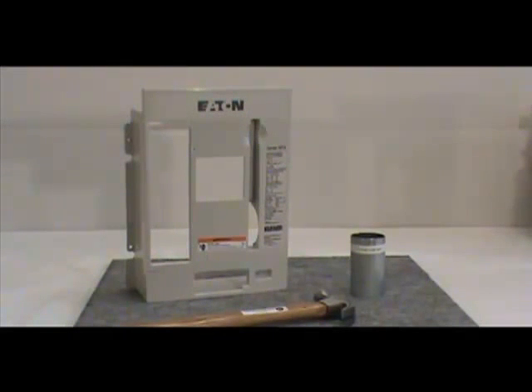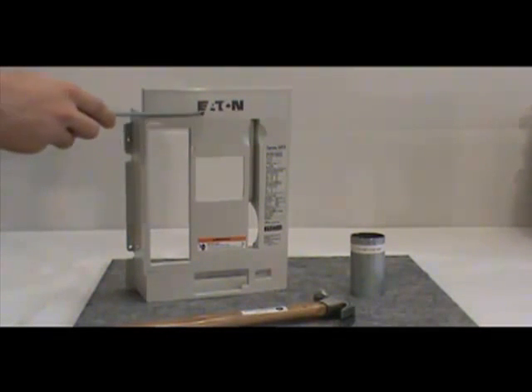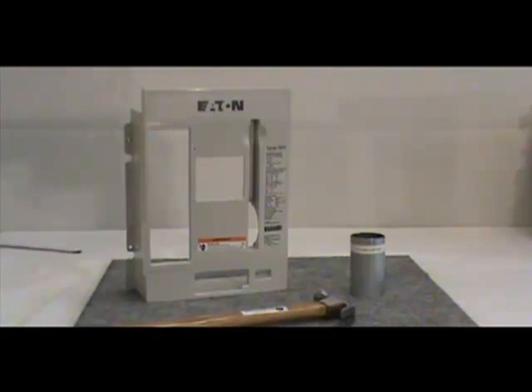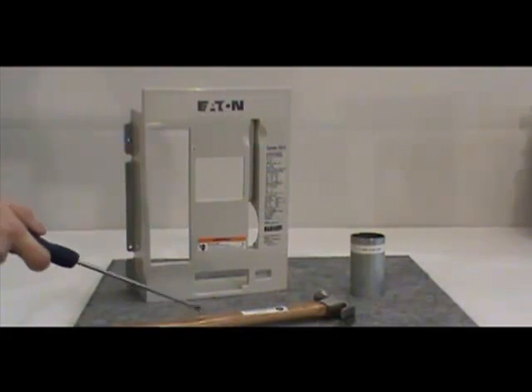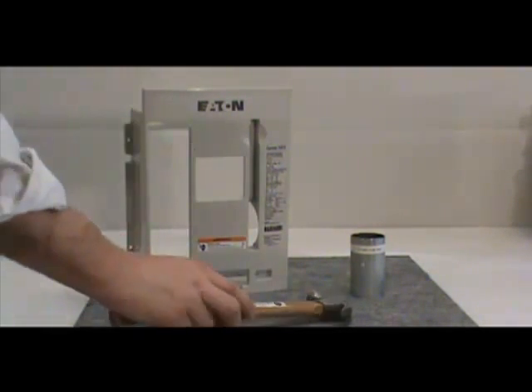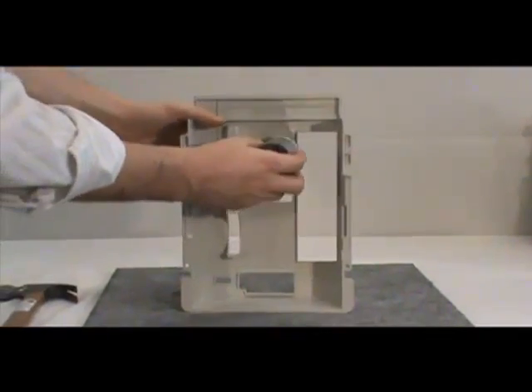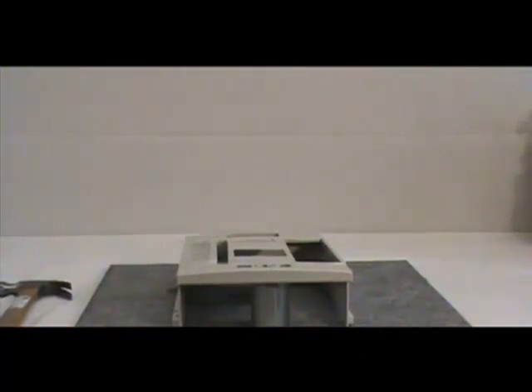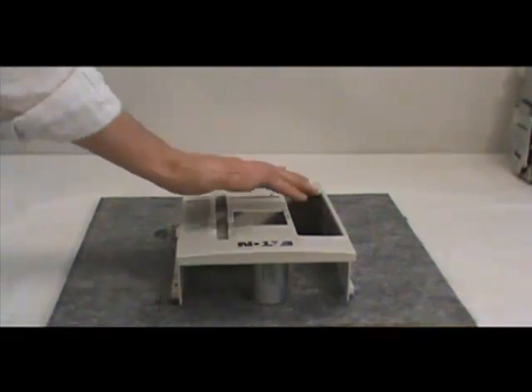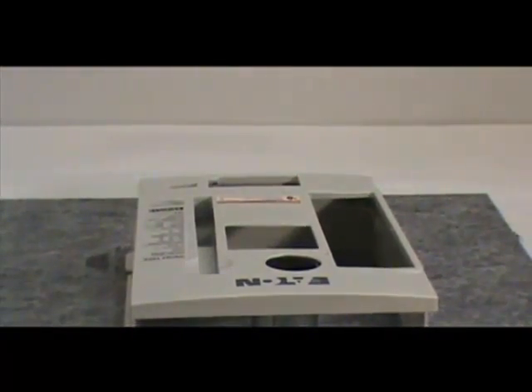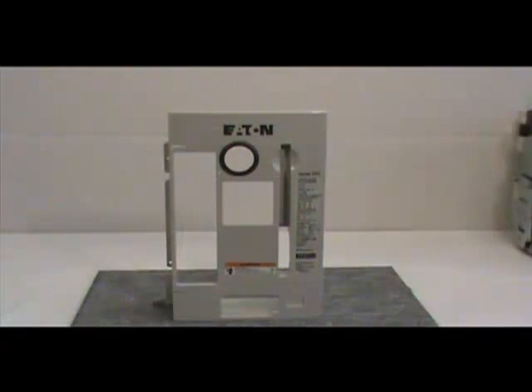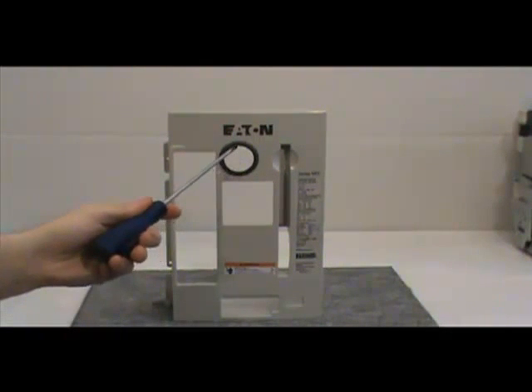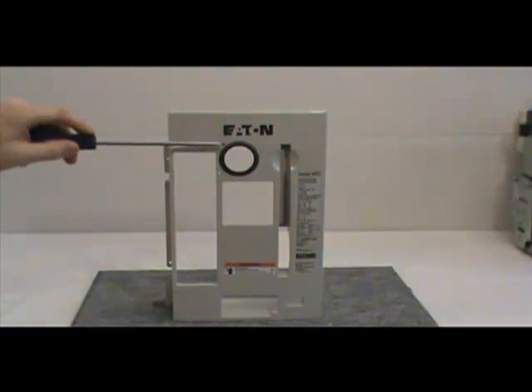In order to punch a hole in the cover, you need a rigid support that is slightly larger than the outline of the hole. In this demonstration, we are using a 1 1⁄2 inch by 3 3⁄8 inch pipe and a hammer. Place the rigid support flush with the hole on the underside of the cover. This will create support and will prevent the cover from splintering since the pipe is slightly larger than the hole. Hit the top side of the hole with the hammer. Make certain that all pieces and or particles are removed from the inside of the hole before proceeding. Once you've punched the hole, attach the external adhesive ring to the breaker.